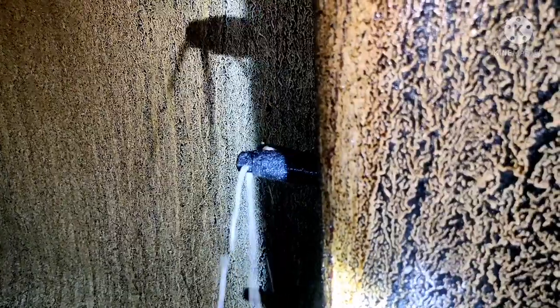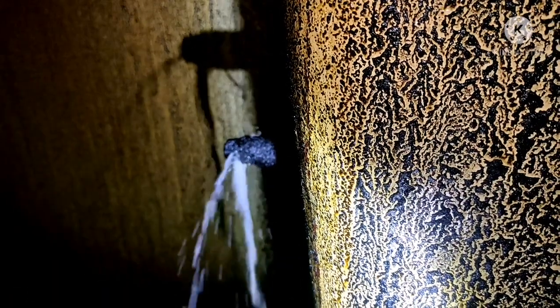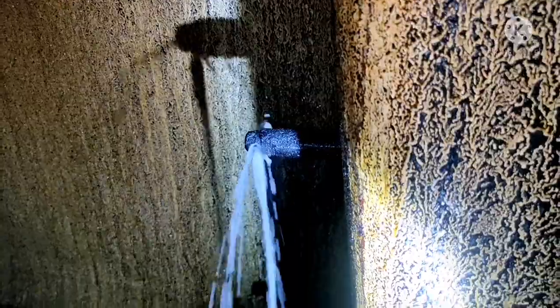You can see the nozzle is choked because I can see flow from only two nozzles. What I need to do is clear the nozzle and clean any deposits. Then I will check again to find the steam coming out properly. Now water is coming because when I open the line, the remaining water in the line will come out first, and later the steam will follow.